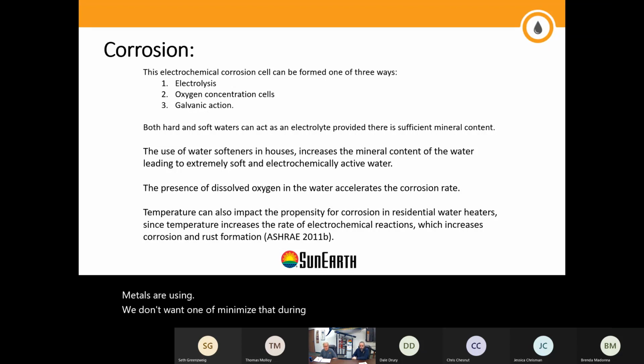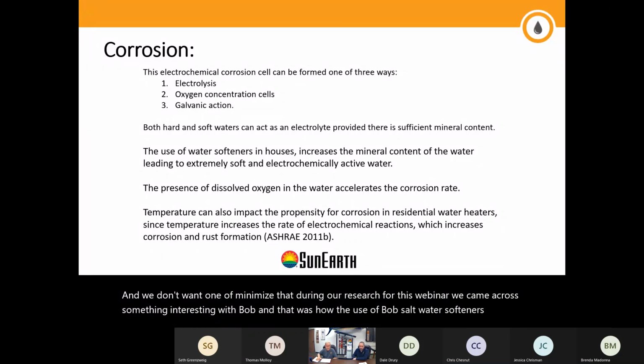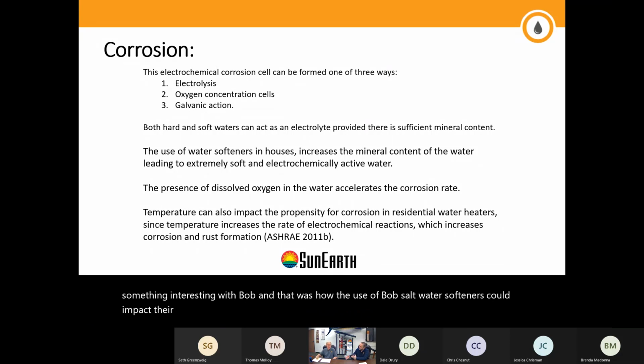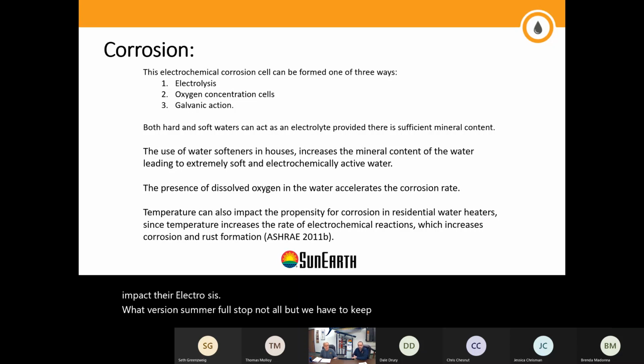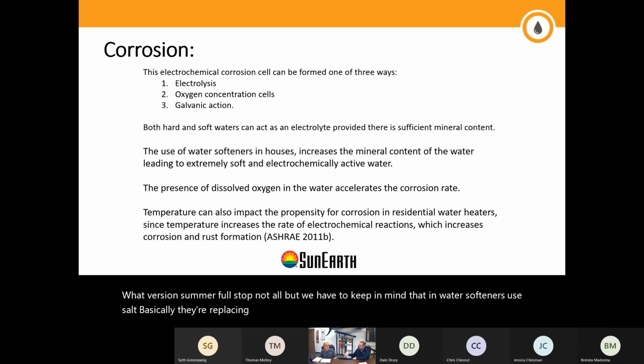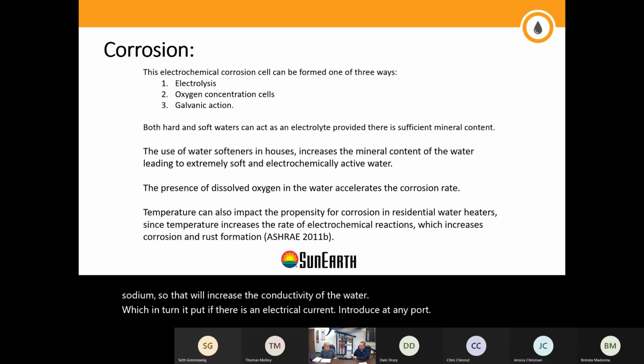During our research for this webinar, we came across something interesting with Bob: how the use of salt water softeners could impact electrolysis corrosion. Some water softeners that use salt replace magnesium and calcium with sodium, which increases the conductivity of the water. If an electrical current is introduced at any point in the system and the water is conductive, you can see corrosion.